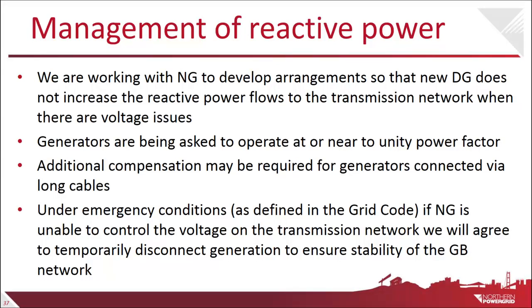So we're looking for solutions where the reactive power flow, the exported reactive power at the grid supply point, is not increased as a result of a generator connecting to our network. Part of our solution is asking those generators to operate at or near unity power factor. But we don't believe those customers should be penalised and have to solve problems that National Grid already has, which was in effect what they were trying to get by the back door. Maybe that's a bit harsh, but in effect they were asking for more than they needed, and we're saying that's a bit unreasonable for our end customers, so we didn't want to go quite that far.